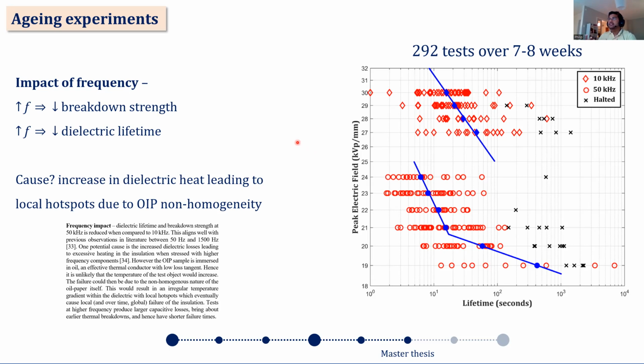But also consider that the test object was in oil, which has very good thermal properties. So what we thought was happening is that even though the overall temperature of the sample is not increasing, due to the non-homogeneity of the paper fibers, increased dielectric heating could cause local hotspots, which would first cause local thermal breakdown and over time global failure of the complete insulation. This is what we thought was the reason. I took a small snippet out of the paper that we are writing which explains this in further detail.